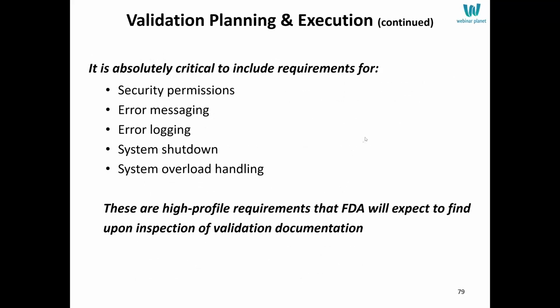The requirements to include and never miss, because these have been the subject of recent FDA findings: security permissions, error messaging and logging, system shutdown and overload handling, and you would test each of these during validation. They're high-profile requirements the FDA would expect to find, and these are non-functional or system requirements.